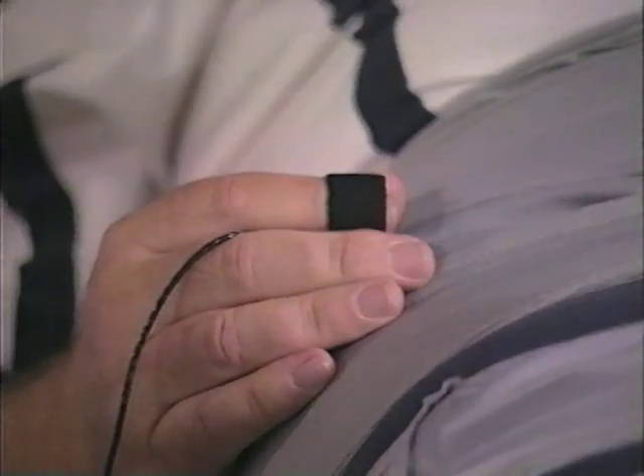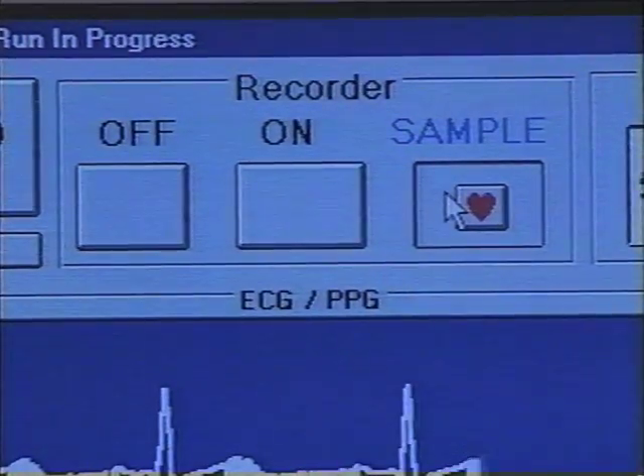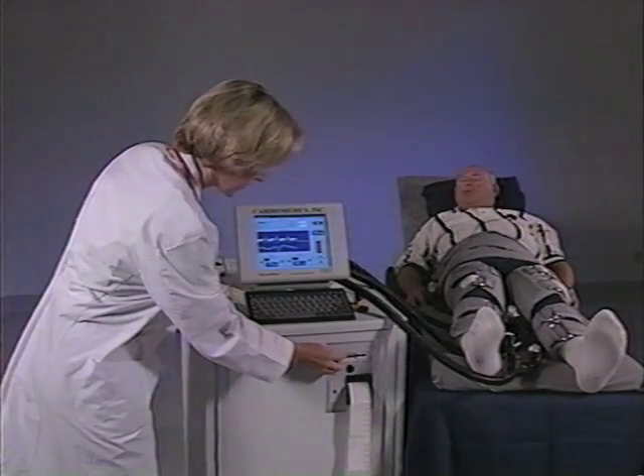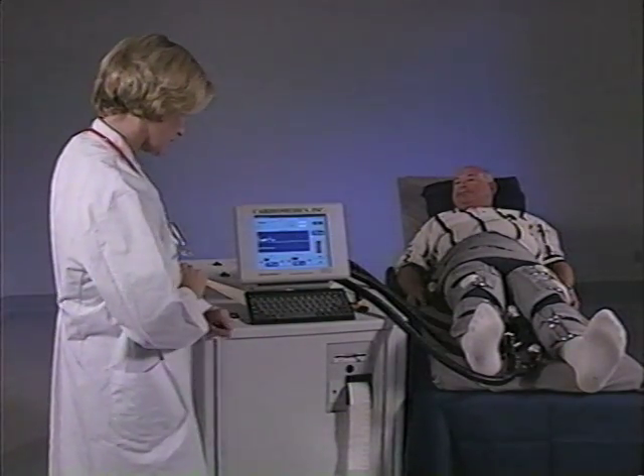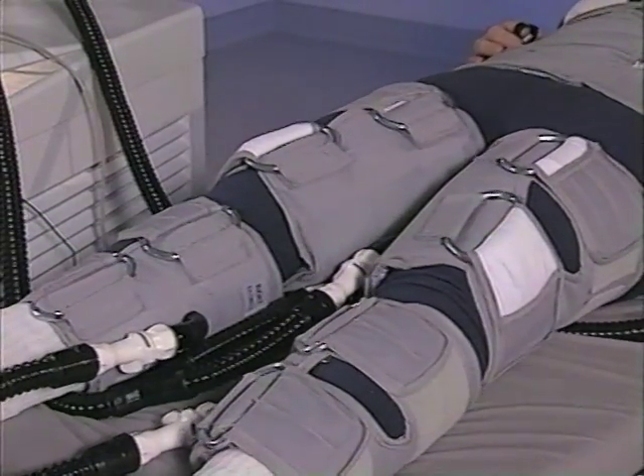Arterial pressure is obtained from a finger plethysmograph and is also displayed on the CardiAssist control panel. The CardiAssist strip chart recorder can produce either a continuous record of the patient's ECG and arterial blood pressure, or can be set to automatically print a five-second sample at the end of each minute of therapy. The patient's ECG and arterial blood pressure are stored automatically on the hard drive, and data may be downloaded to a floppy disk at any time.